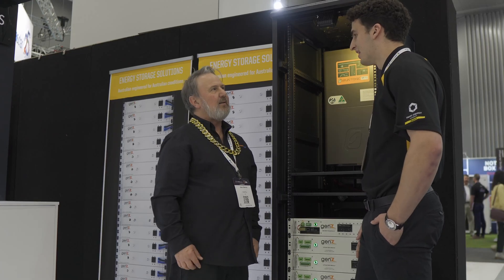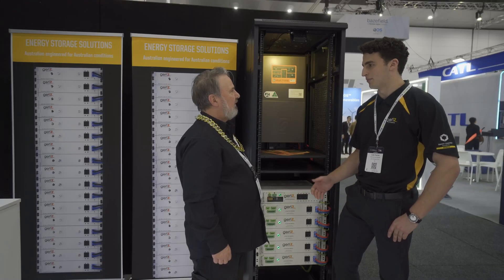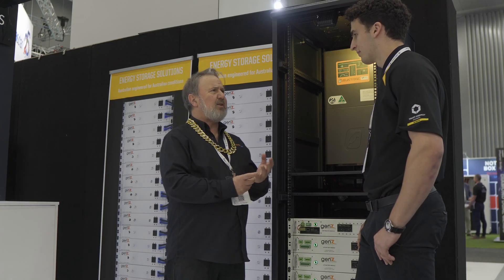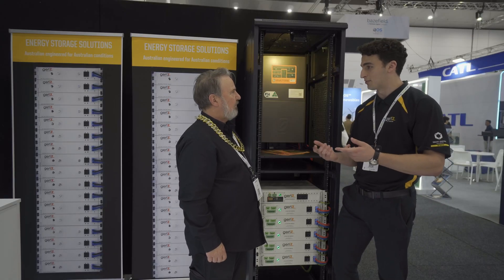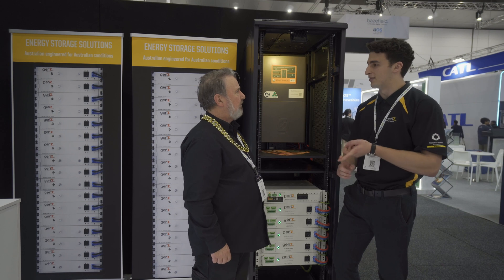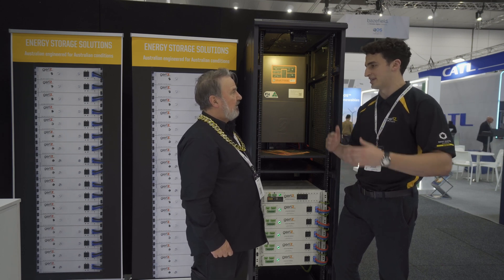What makes it smart? So what makes it smart is that not only does it now manage the cells and keep the battery safe, but it also has a communication layer that gives us an extra level of data that we can read in through our distribution module. So it records things like state of charge, voltage, current, cell voltages, temperatures for two temperature probe sensors. It can also give you state of life, number of cycles, and alarm information based on when those thresholds get exceeded.